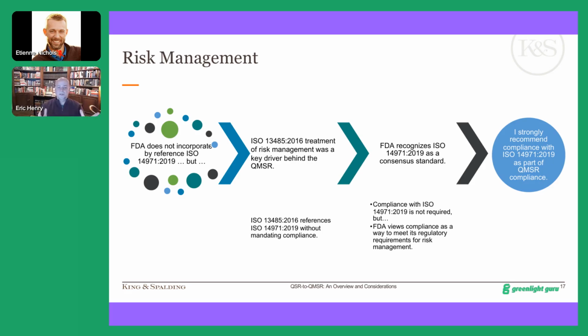In those cases, I always tell people—in fact, I was on the phone with a pharmaceutical client just yesterday talking about risk management and FMEAs—there's no reason for you to do this other than because I told you it's better. But ISO 14971 is better than ICH-Q9, and you should follow it to the greatest degree possible. Line it up with your risk management process and just follow it because it's well structured.